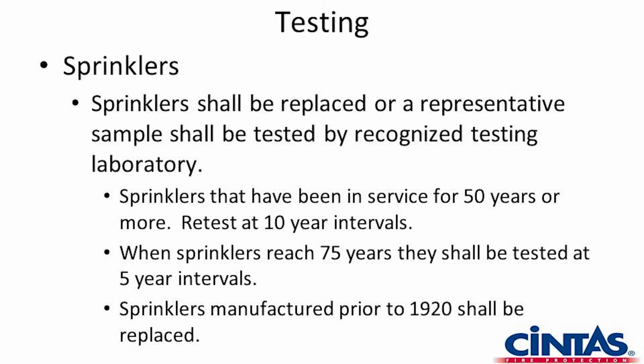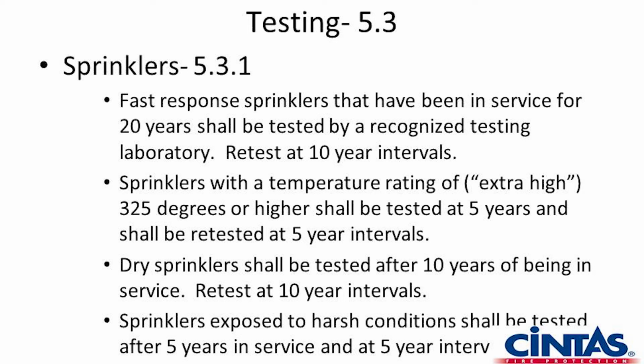Sprinklers shall be replaced or samples tested. UL, like I said, is generally who they go to. Over 50 years old are to be retested at 10 year intervals. When sprinklers reach 75 years, they shall be tested at 5 years. We talked about that 1920. Sprinkler manufactured prior to 1920 shall be replaced. No testing on those. Going into fast response sprinklers, 20 years, they'll be retested at 10-year intervals. Sprinklers with a rating of extra high, which would be 325 degrees or higher, shall be tested or replaced at 5-year intervals and then retested at a 5-year interval.